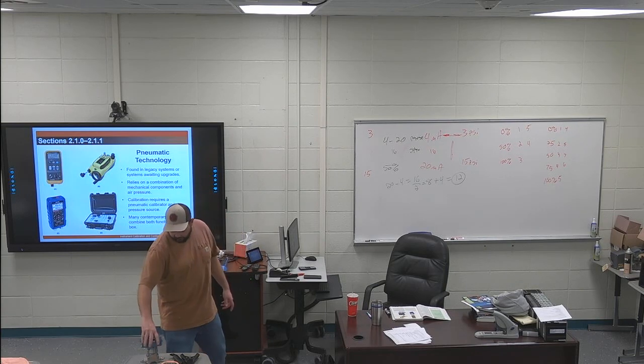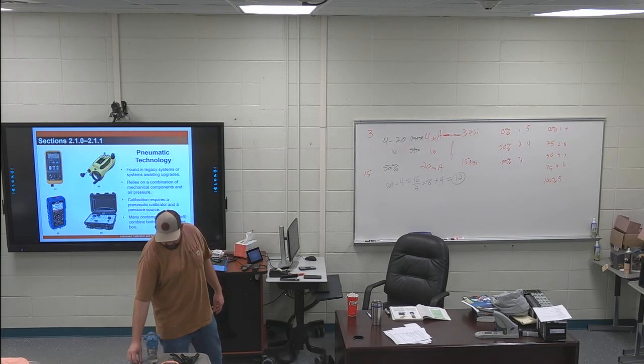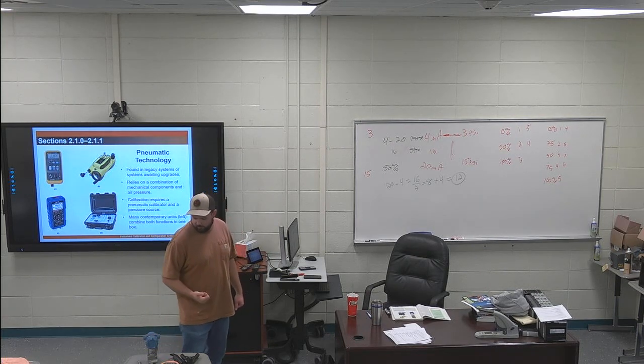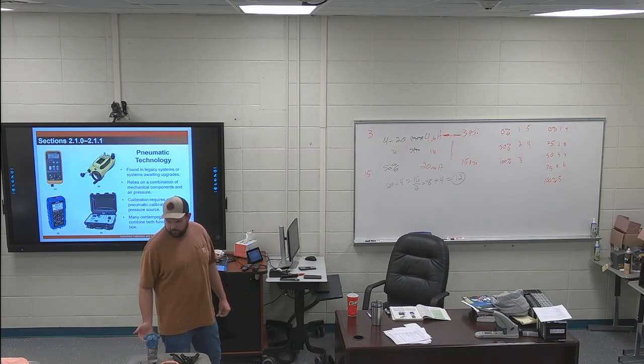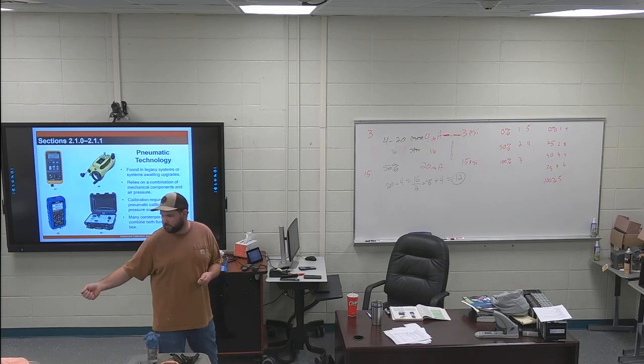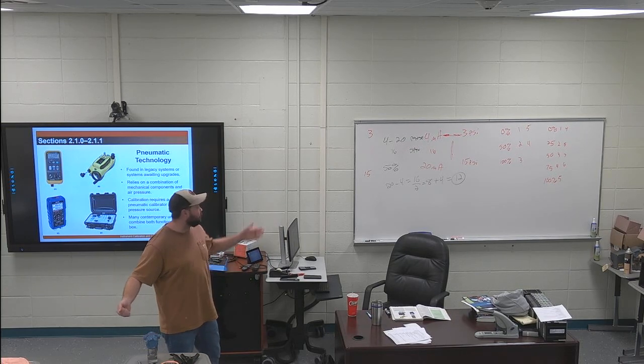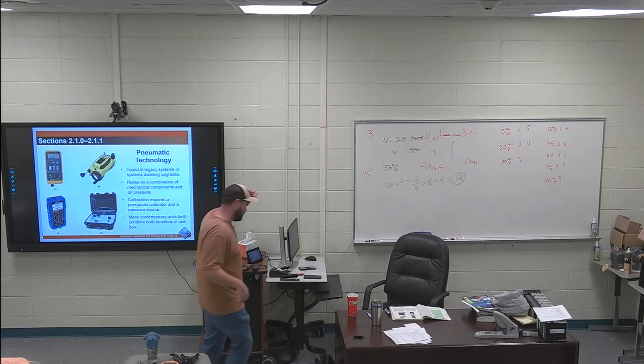But yeah, you literally would go out to the gauge, put your little stinger in, and then you can pump it up. If you don't have an air supply, you can pump it up yourself and say I'm inputting 3, and then make sure that you're getting 4 milliamps on the other side or something like that.